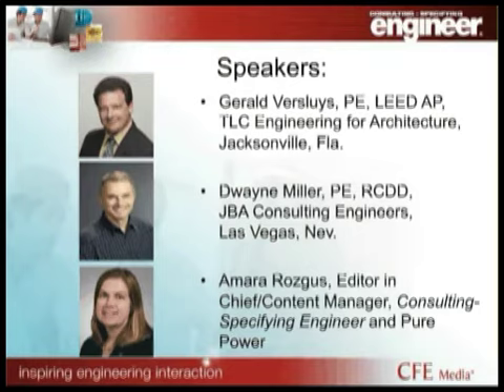When you start talking about generating into the grid, which actually here in Las Vegas, North Las Vegas, Apex is a site where we're actually doing that with a large turbine. That's typically a different type of system than you would have for backup to a property. But as far as demand management and helping the utility out, we've seen that all over the country where, particularly on more remote properties, the utility will call on them in August, or at their peak time, and ask them, hey, can you take some of your load to generator? And they're incentivized to do that. As far as what codes apply, other than 705, it really is going to come down to whatever the interconnect agreement is with the utility.